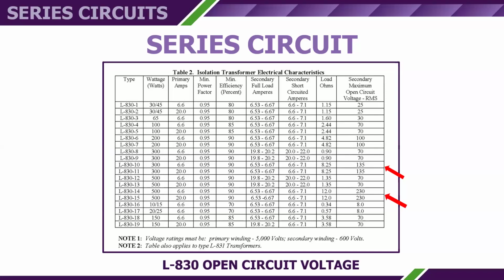OSHA and NFPA 70E set the de-energization threshold at equal to or greater than 50 volts. Anytime you could be exposed to a potential greater than 50 volts, OSHA and NFPA 70E require you to create an electrically safe work condition. And so even down here at a 100 watt transformer, you've exceeded the 50 volts. And remember, if a primary to secondary short occurs, which is a possibility, you could be seeing 5,000 volts out there.